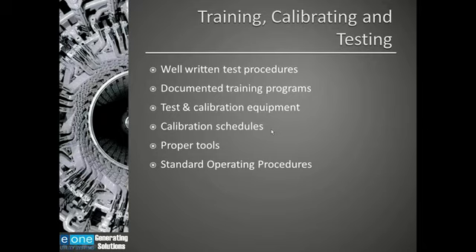Maintain a calibration schedule. Know how often the equipment needs to be recalibrated or tested. I'll give you an example with dew point sensors. Dew point sensors need to be recalibrated every year. And they cannot be done in a power plant. They need to be sent back to the manufacturer in order to be recalibrated. And the problem with them is they could give you a negative low reading. So it's important to know that although these sensors may look like they're giving you a good reading, they could be out of calibration. So you need to have a calibration schedule.